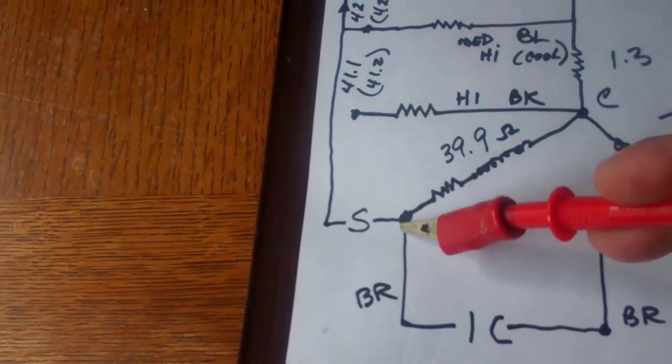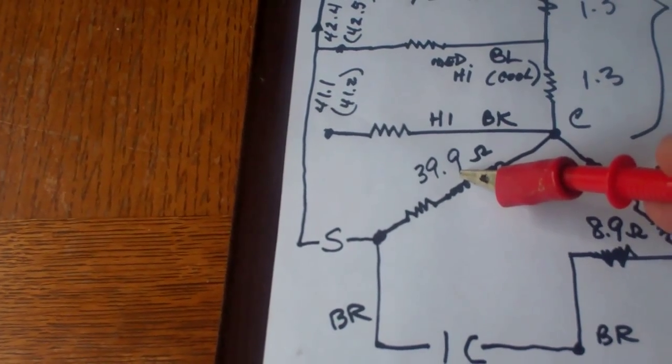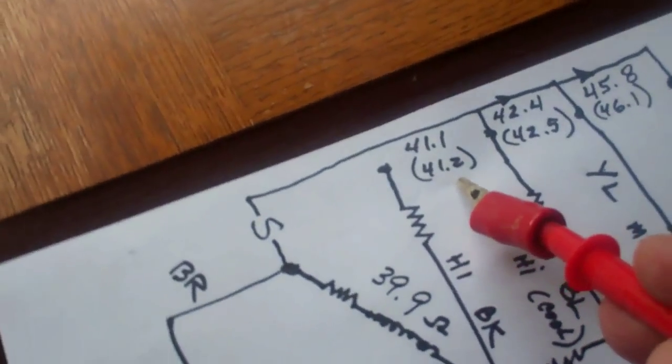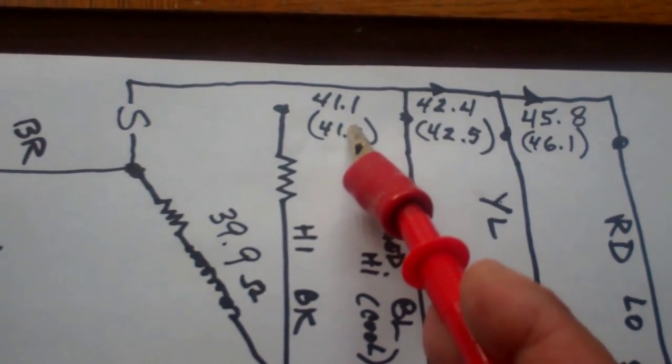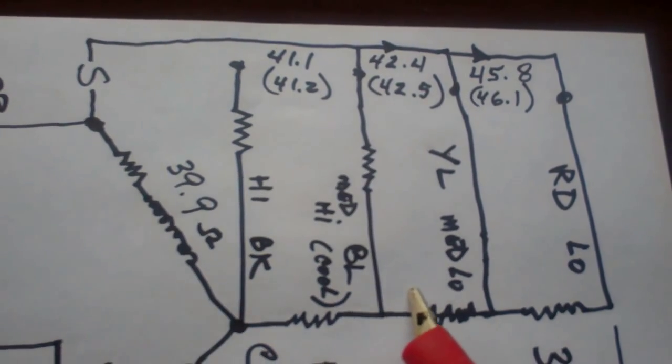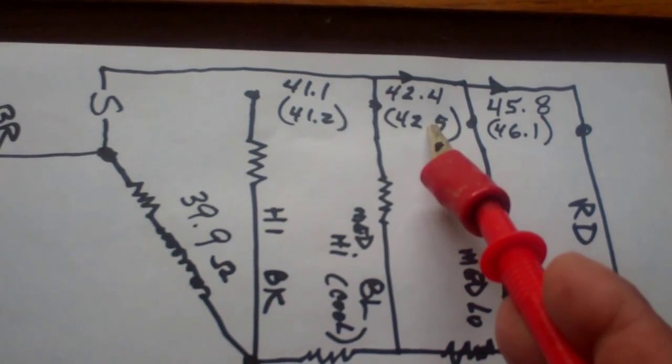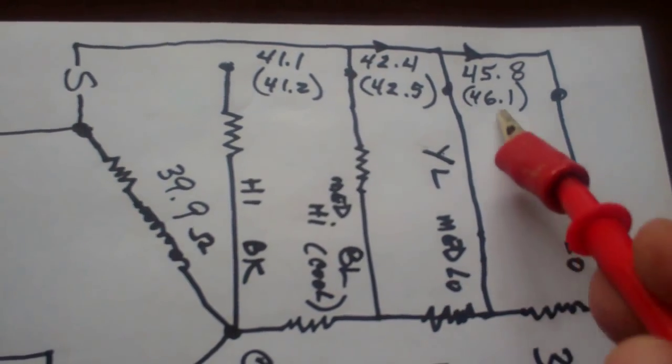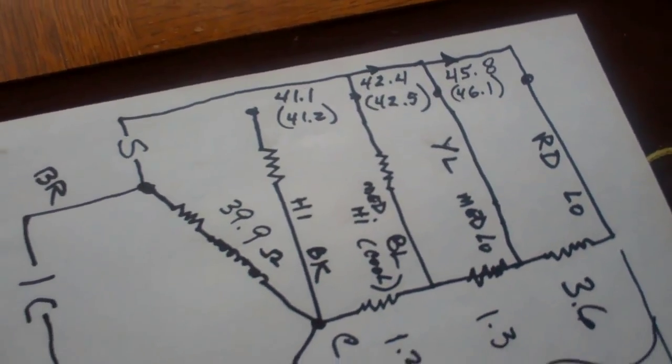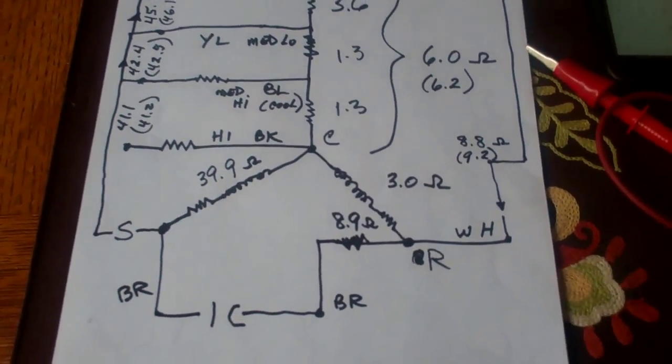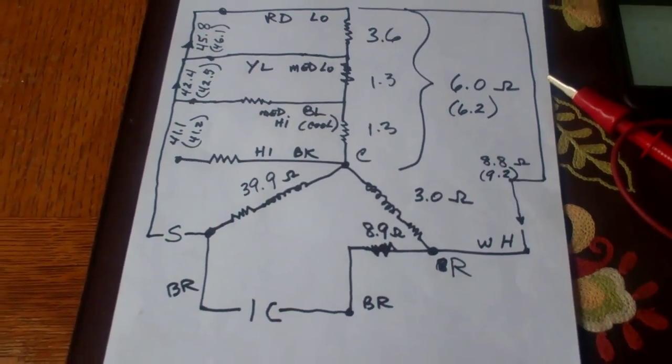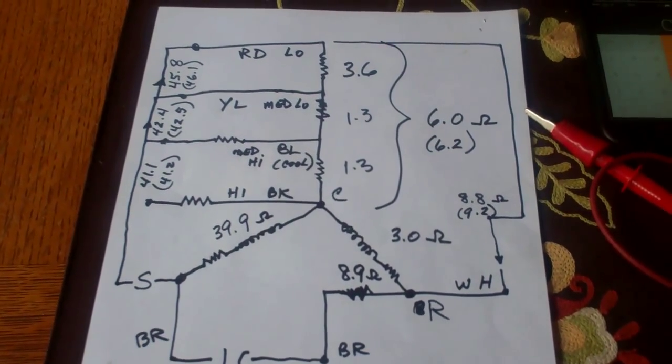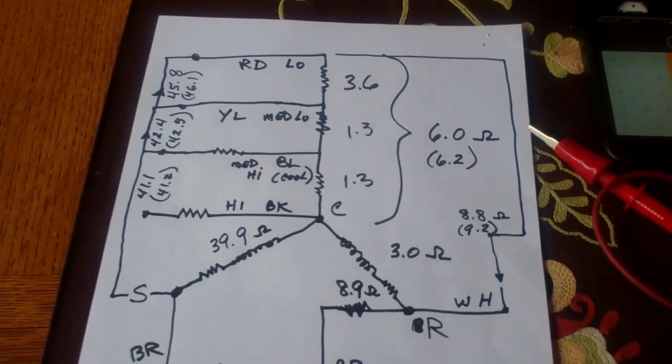And you can see I did, here's brown. So brown to black was 39.9. So if I went brown to blue, I'd be looking for 41.2. I got 41.1. From brown to yellow, I'd be looking for 42.5. I got 42.4. And from brown to red, I'd be looking for 46.1. I got 45.8. Very close. So I'm happy with all those readings. It all makes sense. They all add up. There's no reason why this motor shouldn't work. And it spins freely, so the bearings aren't shot on it. So we're going to throw that motor back on.